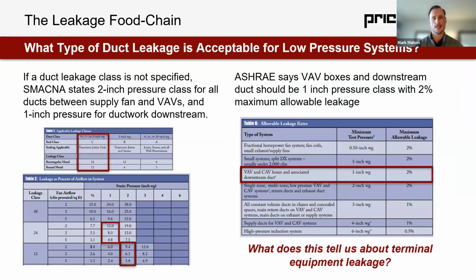And Tom spoke to this in length, so I'll just give my 2 cents really quickly and start off with SMACNA. SMACNA's recommendation, or what they state, is if the engineer is not specifying a particular duct leakage class or a duct seal class, it should be a 2-inch pressure class for ductwork between supply fans and VAVs and a 1-inch pressure class for ductwork downstream. So that would mean seal class C, those transverse joints, essentially a slip and drive. We're going to seal a slip and drive. And that's going to mean the leakage class for that ductwork is, for rectangular ductwork, 24. Now, my argument would be that leakage class is too low.